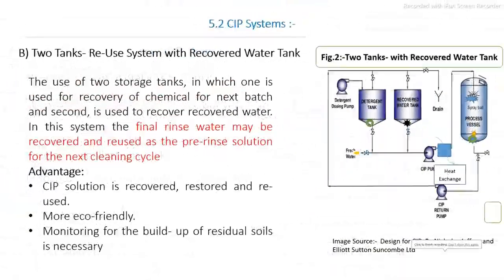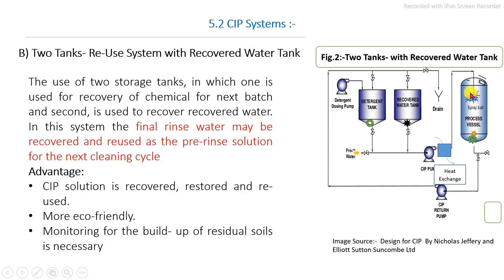The second one is the two-tank reuse system with a recovery water tank. In this process, the two-tank CIP system has two main tanks: first, the detergent tank, and second, the recovery water tank, with processing pumps, fittings, piping, valves, and a heat exchanger for heating water. The pre-rinsing water, final rinsing water, and detergent solutions are managed through this system. The final rinse water may be recovered and used as pre-rinsing solution for the next cleaning cycle.